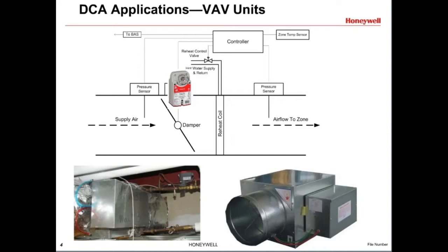Since the actuator in VAV boxes moves the damper only slightly in response to the temperature changes, it usually does not fully open or close the damper. Because of this, VAV boxes generally specify design life of the actuator by the number of actuator repositions, not full open or close cycles. All Honeywell DCAs are rated to provide at least 1.5 million reposition strokes.